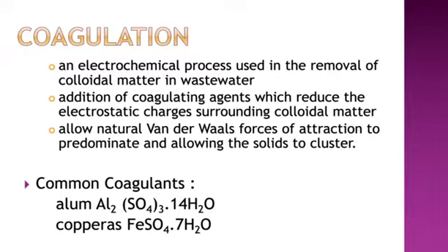And we are going to add coagulants, or coagulating agents, that can reduce the electrostatic charges surrounding the colloidal matter. And then we allow the natural van der Waals forces of attraction to predominate and allow the solids to cluster. These are the common coagulants: alum, or what we also call tawas, and copperas.